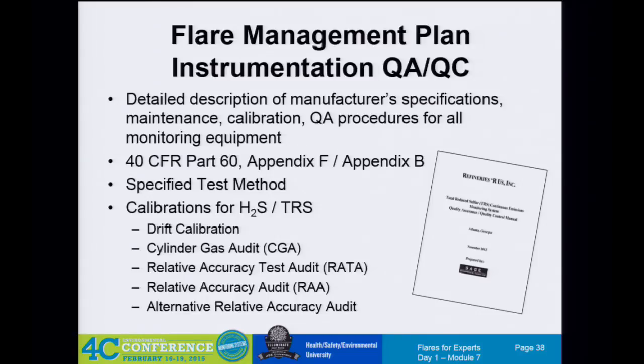So can the baseline be zero? Yes, so if you have a flare gas recovery system that's sized to capture all routine flows, you're pretty much looking at 0, or your purge gas rate, unless you have some routine event that's going to cause the compressors to be taken out of service. Well, the purge is going from the water seal to the flare, and the flare gas recovery is sucking everything else back. And it's not reportable until it's 500,000 or above.